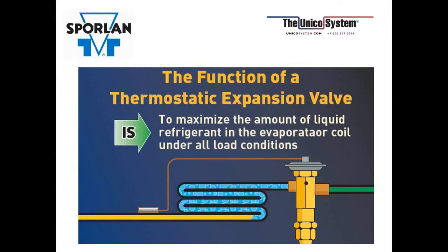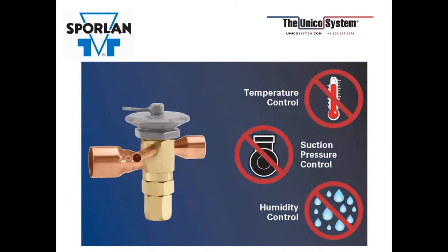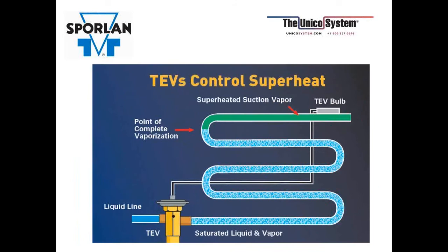The function of a thermostatic expansion valve is to maximize the amount of liquid refrigerant in the evaporator coil under all load conditions, and it does this by controlling superheat. So that means it's not a temperature control device, it's not a suction pressure control device, and it's not a humidity control device. It only controls superheat.